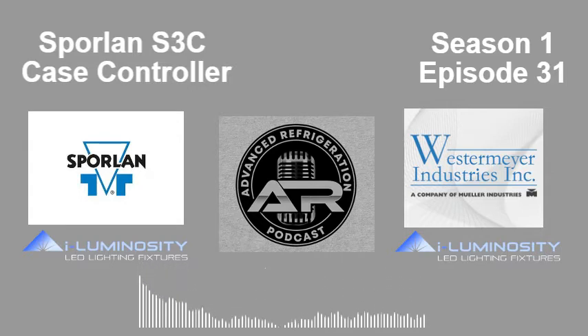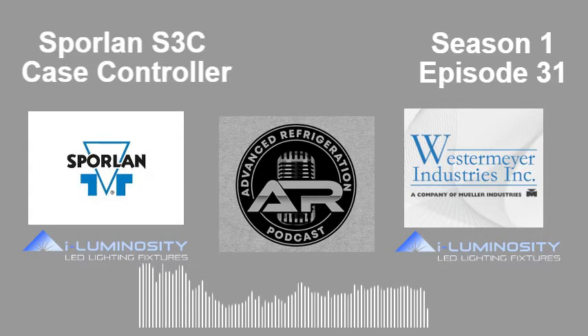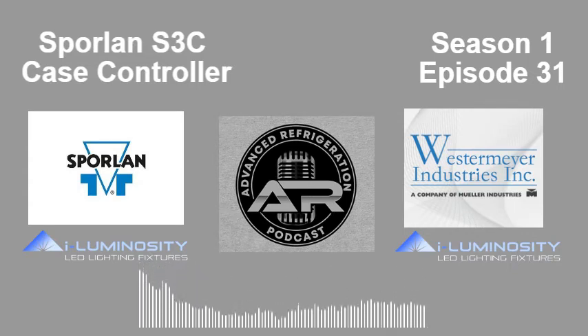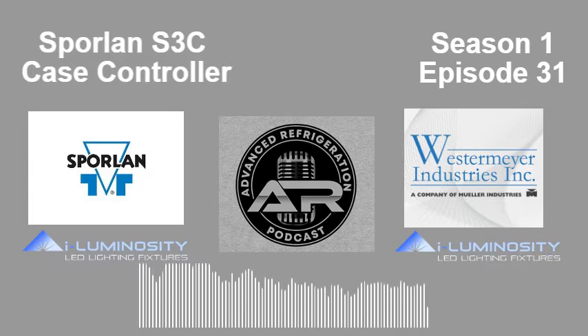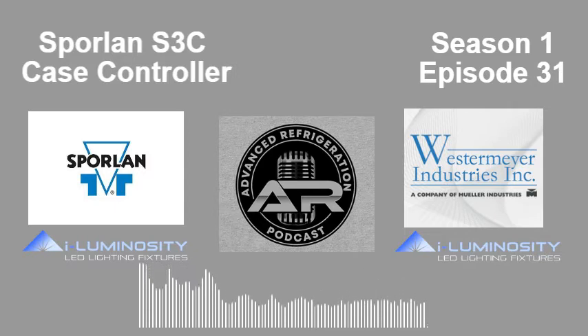Defrost termination is another thing that comes into play. We've got a checklist, a case controller site functional performance test, with up to 11 different functional tests that we suggest you do, ranging from case defrost. If all cases on the circuit go into defrost and you're not getting the expected results, what do you start checking? It lists out step by step. What would you consider? Check the communication wires between the case controllers.